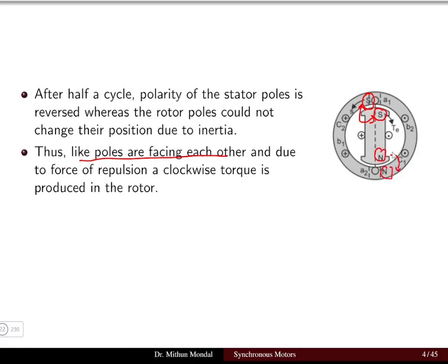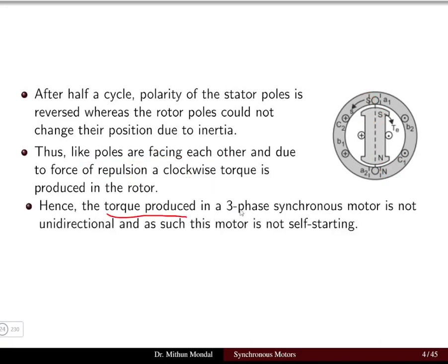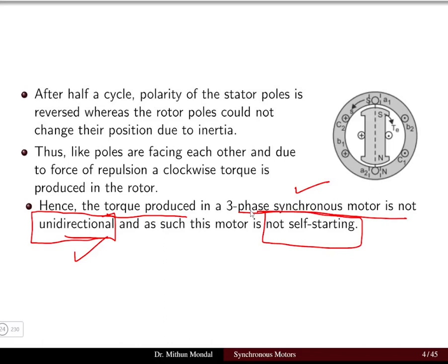When like poles face each other there is a force of repulsion and a clockwise torque is produced in the rotor. First the torque was anti-clockwise, and now it is clockwise. Hence the torque produced in a three-phase synchronous motor is not unidirectional, indicating that the motor is not self-starting. So the motor cannot start on its own as a three-phase induction motor does.